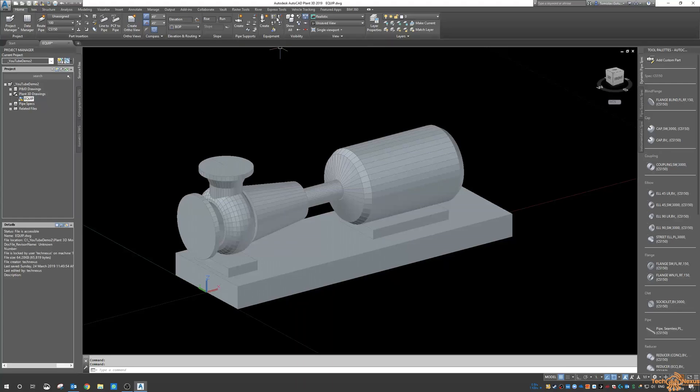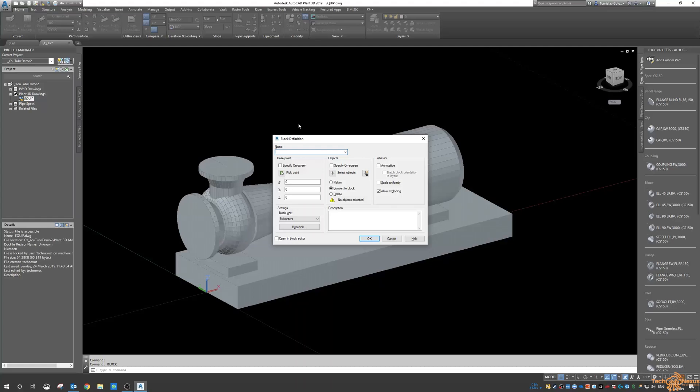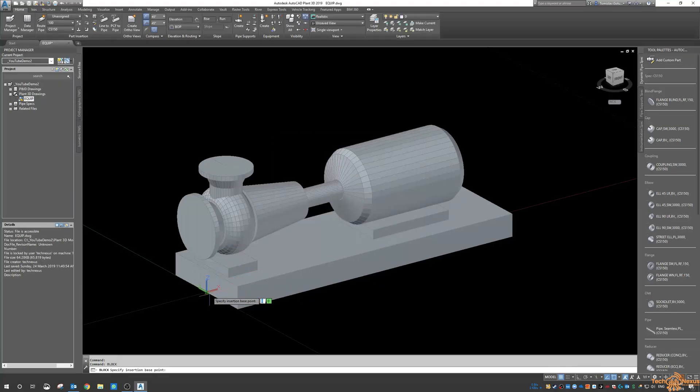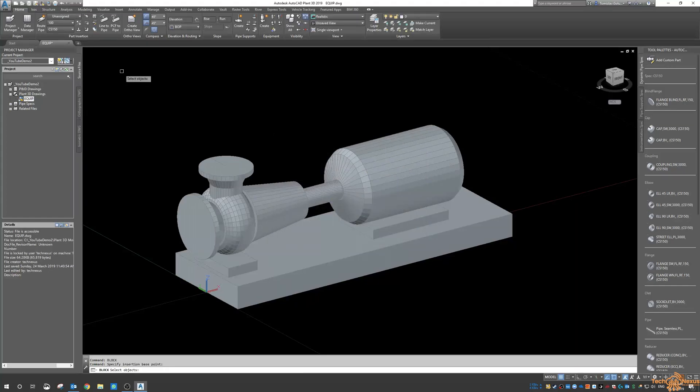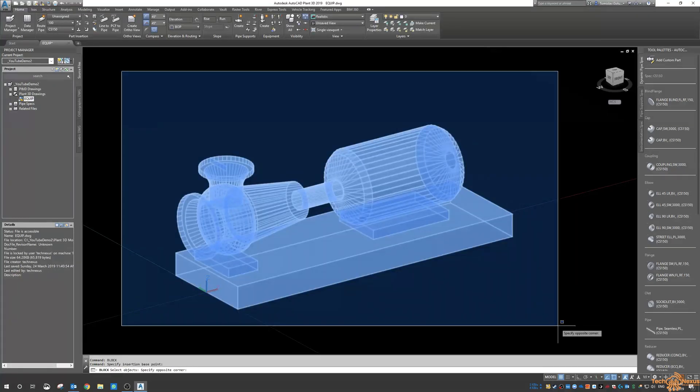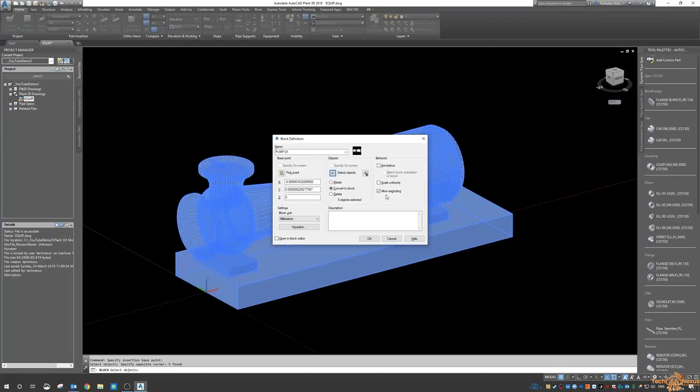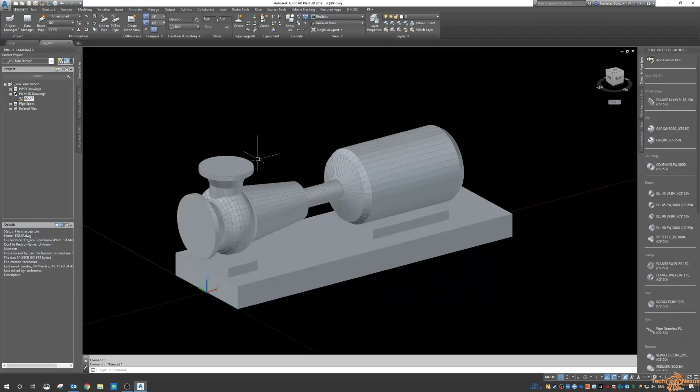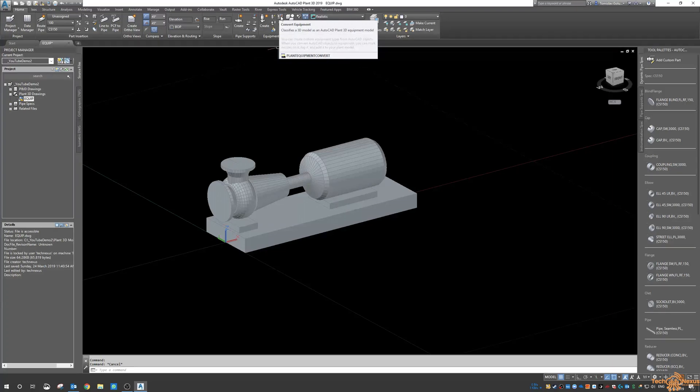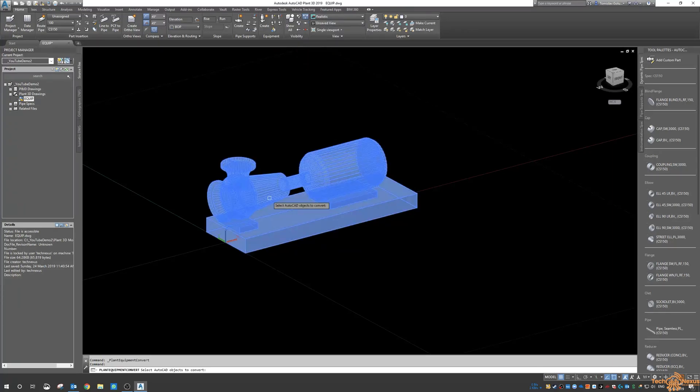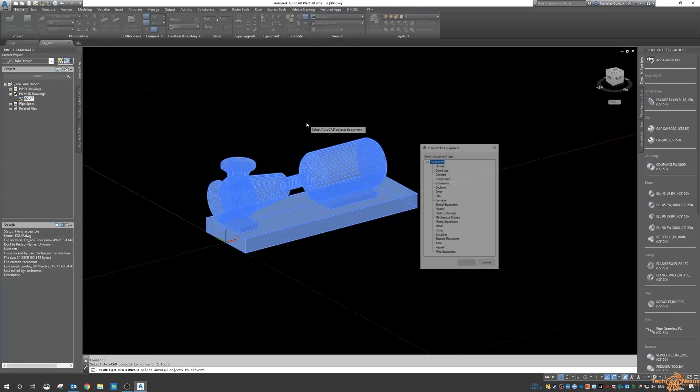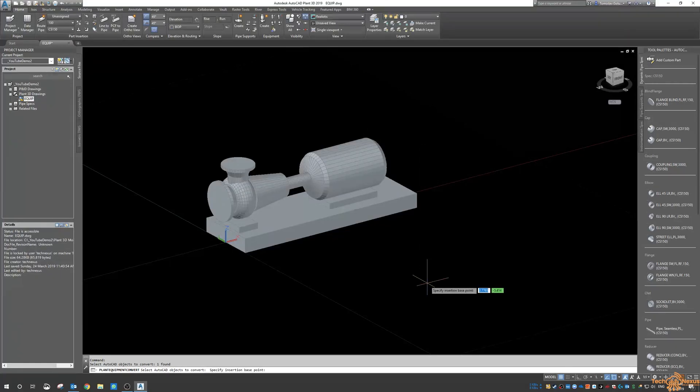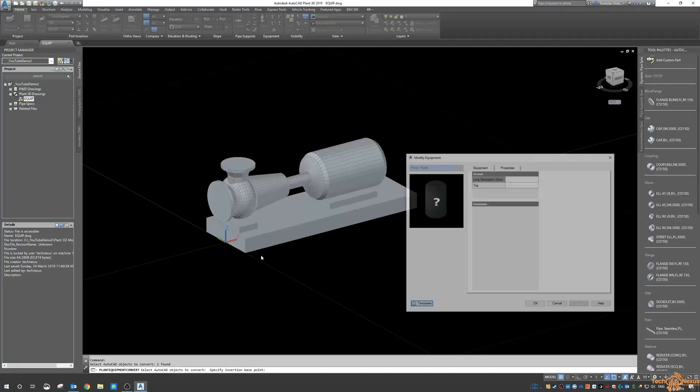So if we wanted to convert the equipment, I'll need to make it a block first. And I'll call it pump-01, pick a base point, select the objects and then go okay. So now that's a block. Then up here in the Plant Tools and under the Equipment tab, we convert equipment. I select the block, make it a pump for the class and go okay. The insertion point is the midpoint there and then we can give it some properties.